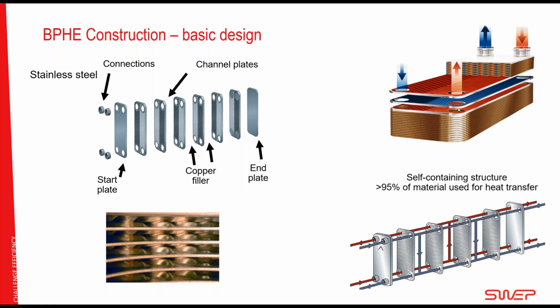Once they are produced, you will see that like any plate heat exchanger, we have alternating hot and cold channels. So 2 plates make 1 channel, and every 2 new plates make another channel, where there will be alternating warm and cold media. So it becomes a very large surface area with very efficient heat transfer. And since there is no plate and frame around it, it's a self-contained structure, so about 95% of the material will actually be used for heat transfer. Here is also an image showing the different plates: cold, hot, cold, hot. Just to give you an idea. We'll come back to this later. This will be important later on.